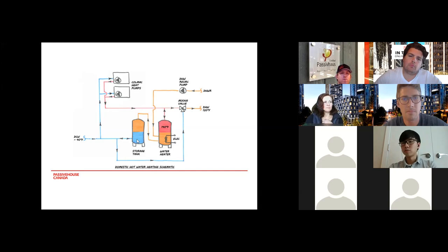So why is this good? Basically, it increases the efficiency of the Colmac heat pumps, which want to see a lower entering water temperature. Secondly, it reduces the cycling of the heat pump by ensuring the Colmacs have a long enough runtime before turning off. And lastly, it mitigates the risk of the heat pumps tripping on high water temperature.